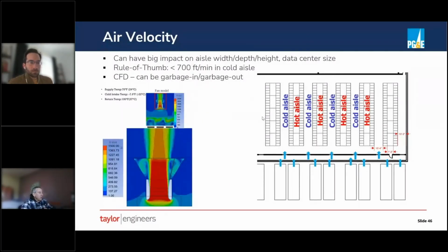Okay, another important environmental criterion for computers is air velocity. Generally, you want to keep your cold aisles positive to your hot aisles, but it's also important not to be blowing air at a velocity that's too high. So here's a typical flooded aisle arrangement. You've got air handlers feeding into a supply plenum and then air going from the plenum through a damper down the cold aisle. The area of concern is the velocity as it enters this aisle.